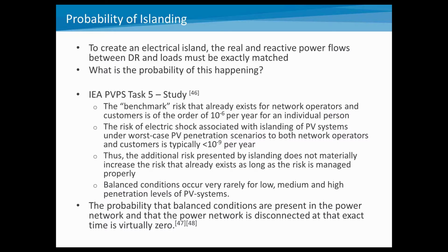So this is something that is obviously a discussion topic that's been around for a number of years. And there was actually a study done out of the IEA, IEA PV Power Systems Task 5, that looked to benchmark probability of islanding. Because the fact is, no matter what kind of distributed generation you potentially have, to create an island that sticks around and sustains itself, you have to have a very closely matched real and reactive power balance. And over time, that power balance can't change. So if all of a sudden you have a lot of load and a small distributed generation, that distributed generation isn't going to be able to maintain an island.